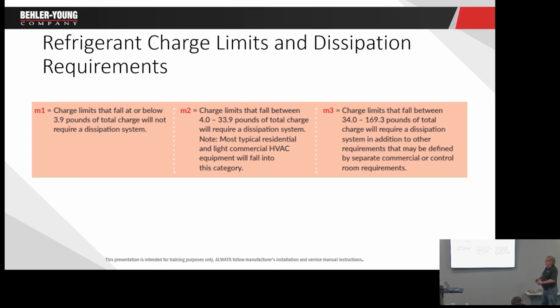Okay, so charge limits. Now, there are limits on how much charge we can put in these. This is all part of the new code. Under 4 pounds, I don't need to do anything special. So we will have some small package equipment that does not have any mitigation system on it, a little through-the-wall stuff, like PTACs, things like that. So they hold less than 4 pounds. Splits can hold less than 4 pounds, depending on how long the line set is, but they can also hold over 4 pounds, so they'll all have the mitigation system we're going to talk about.